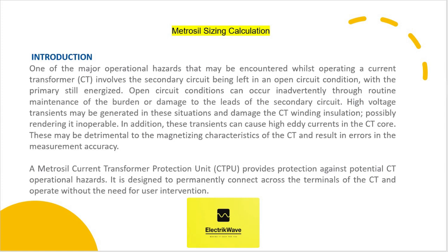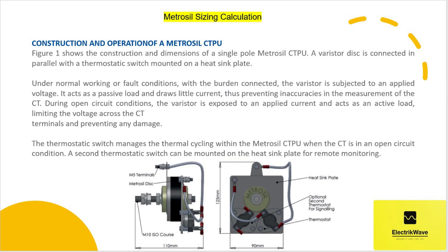Next. Let's see construction and operation of a Metrosil CTPU. Figure shows the construction and dimensions of a single-pole Metrosil CTPU. A varistor disc is connected in parallel with a thermostatic switch mounted on a heat sink plate. Under normal working or fault conditions, with the burden connected, the varistor is subjected to an applied voltage. It acts as a passive load and draws little current, thus preventing inaccuracies in the measurement of the CT.